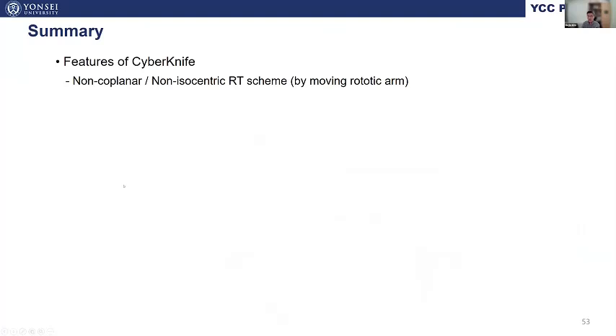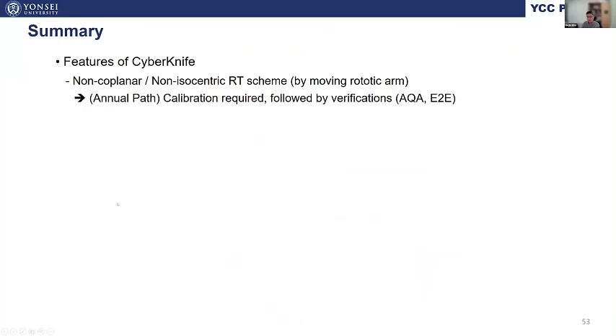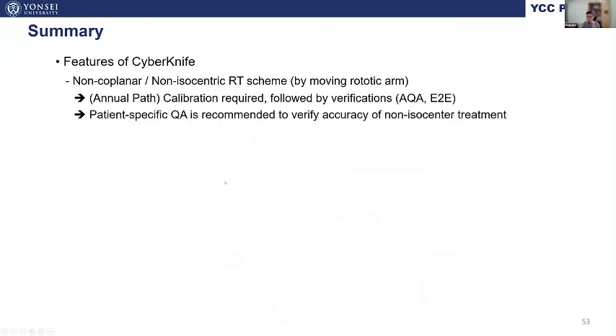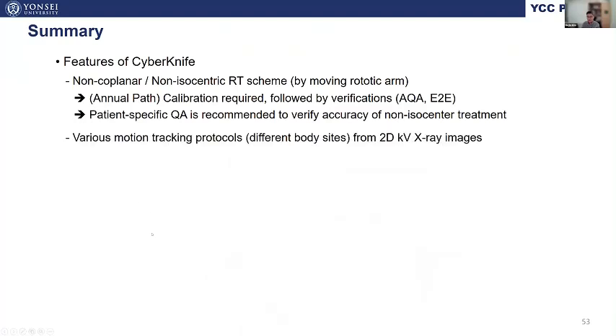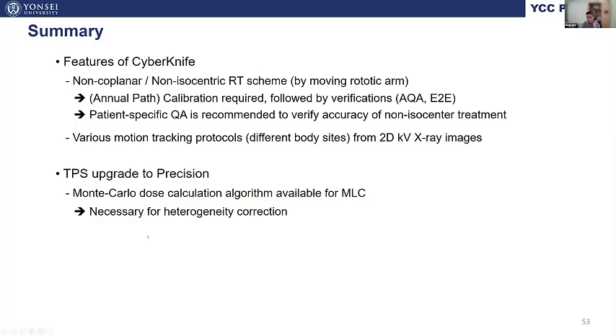So thus far, I've been looking into the features of CyberKnife characterized by its non-coplanar and non-isocentric configurations. To guarantee its accuracy, annual path calibration must be performed, followed by a QA process for verification. It is important to remind that patient-specific QA is the only way to make sure the confidence of the non-isocentric treatment. Various motion tracking protocols for most body sites throughout 2D kV X-ray images are another fascinating point. TPS upgrade to a Precision TPS is totally recommended so that Monte Carlo dose calculation algorithm can be used for the MLC collimator. This is required for heterogeneity correction as mentioned earlier.